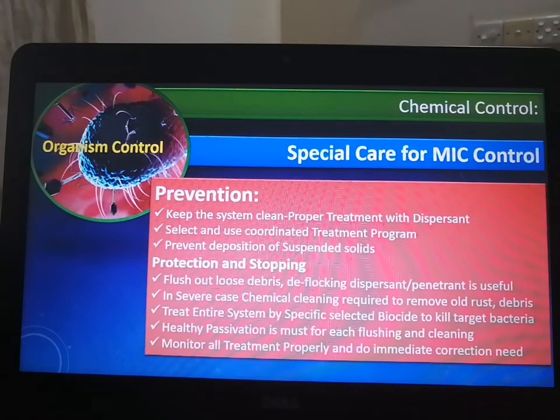If MIC already happens because of mistakes, then we have to flush out the loose debris. If it is rust, sometimes we might stop the system, sometimes we might go for chemical cleaning, because it's vitally important. If we don't take care, the heat exchanger will fail, the tube will leak, and big damage will happen. Maybe we'll have to change the heat exchanger or shut down the plant for a long time, creating a lot of challenges.